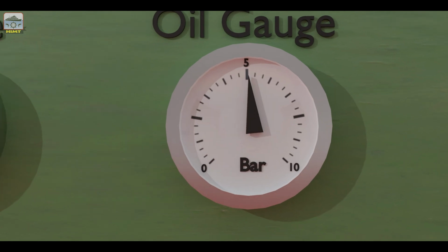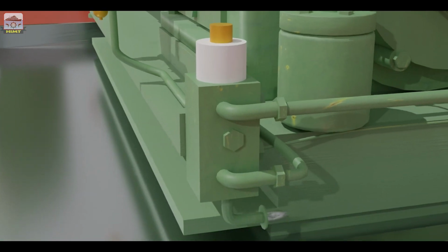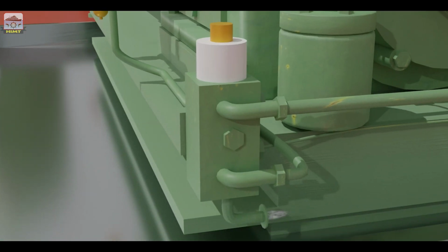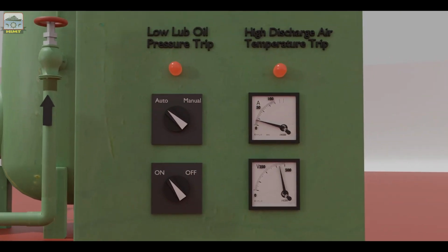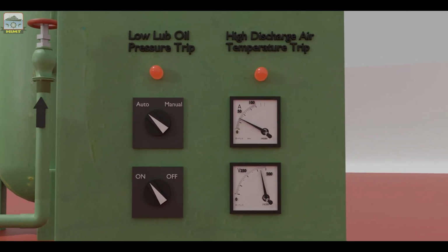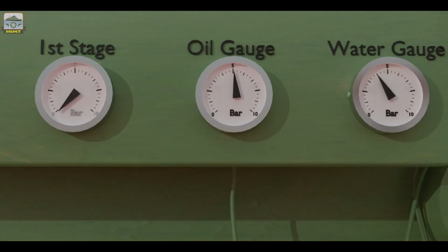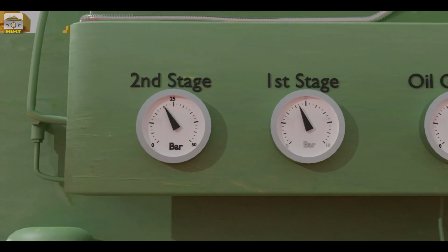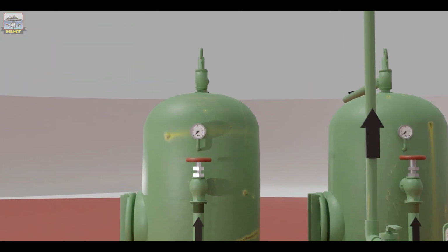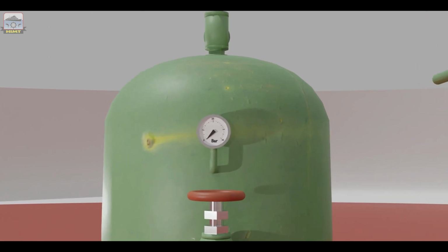During starting, the unloader valve opens, and the air from the first and second stage separator pots is discharged, keeping the load on the motor low. Once the unloader valve closes, the amperage increases, the first and second stage pressure gauge readings go up, and the compressor starts building up pressure in the air receiver.